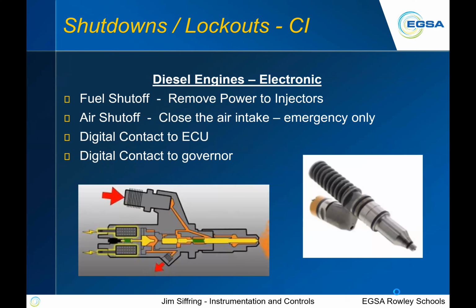Diesel and electronic engines. So how do we shut off fuel to an electronic engine? Of course, we can shut fuel off. On a modern diesel engine, typically an injector is really just kind of a valve. So if we don't energize the valve, it can't inject fuel into the engine. Again, we can shut off air going to the engine. We can do a digital contact to the ECU, which would tell the injection to stop working. We can put a digital contact to the governor, which would cause it to go to zero. Different ways such as that.